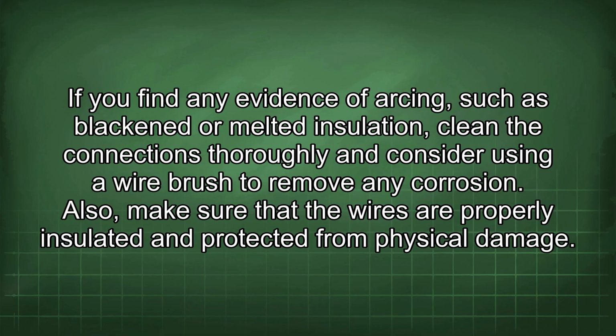If you find any evidence of arcing, such as blackened or melted insulation, clean the connections thoroughly and consider using a wire brush to remove any corrosion. Also, make sure that the wires are properly insulated and protected from physical damage.